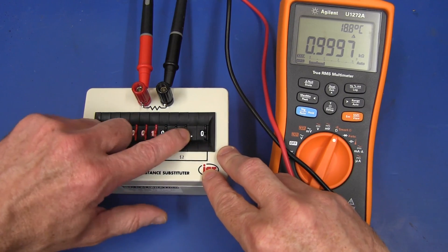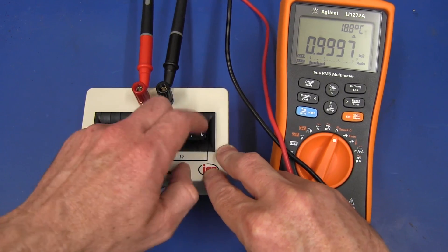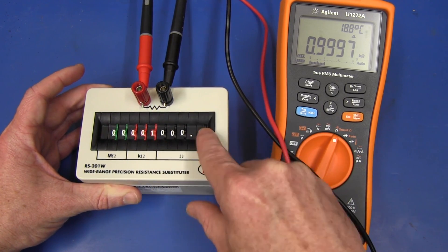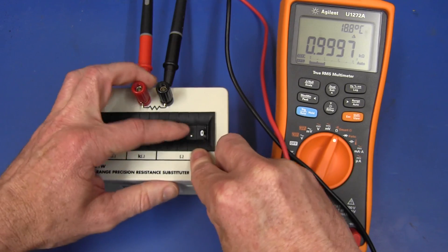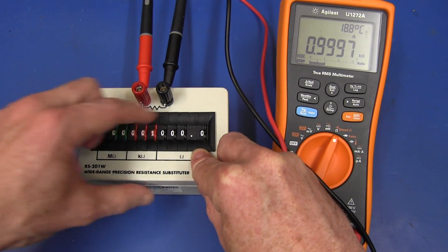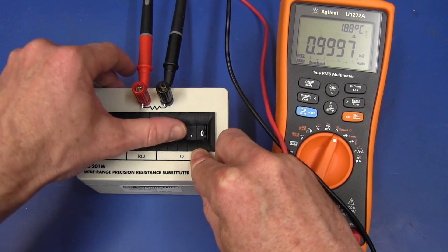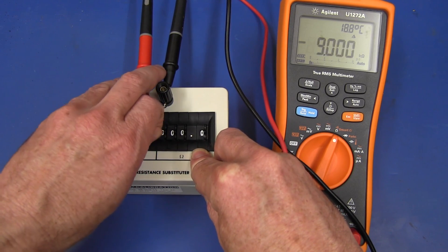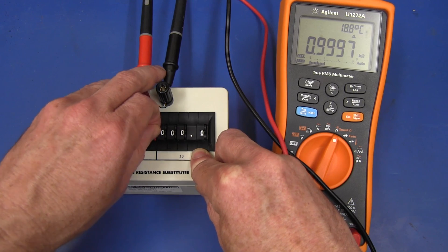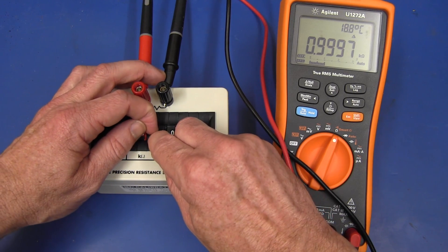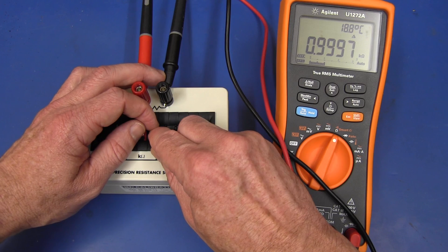Now, I'll just check for dicky switches here. If you go along and you sort of give them a little flick and a little bit of a wobble, does it change? And no, because you'd expect those switches to have good quality spring contacts in them, that actually retain a good low resistance over the range. And if I wiggle that one back and forth just a little bit, then it doesn't change at all unless we actually flick it over, bang, to the next one.